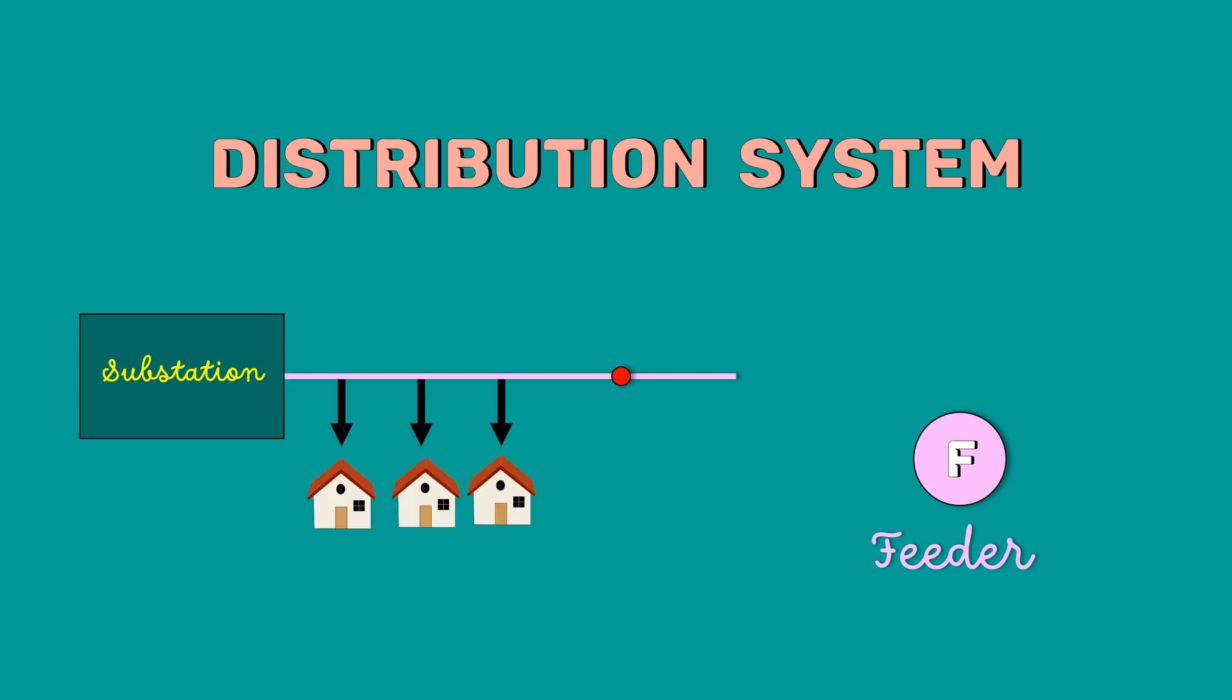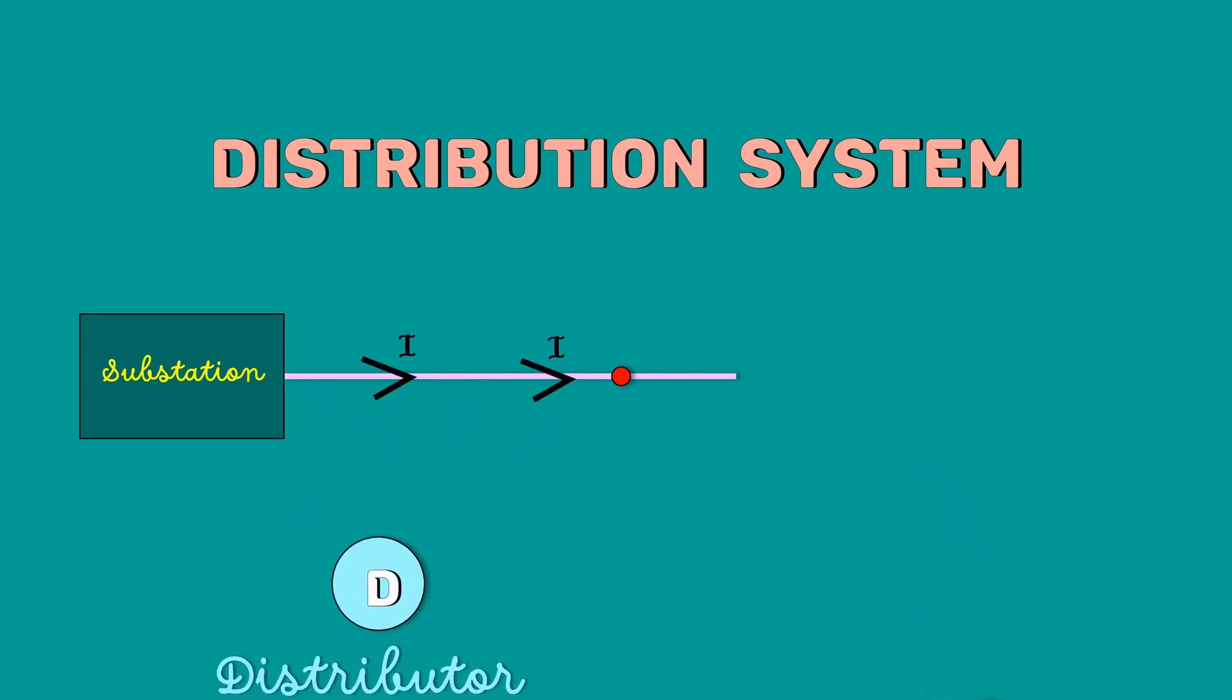The distribution system consists of feeders and distributors. The feeder connects the substation to the area where the power is to be distributed. Generally, no tappings are taken from the feeder so that the current in it remains the same. The tappings are taken from the distributor for supply to consumers.